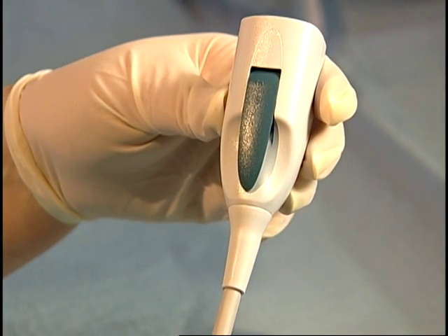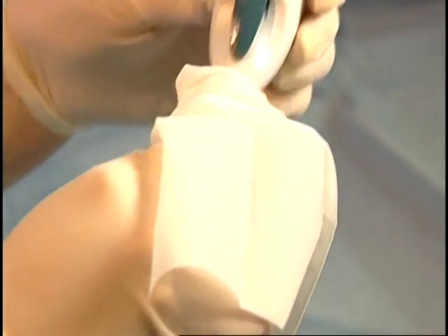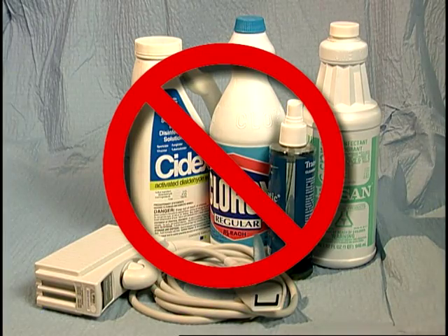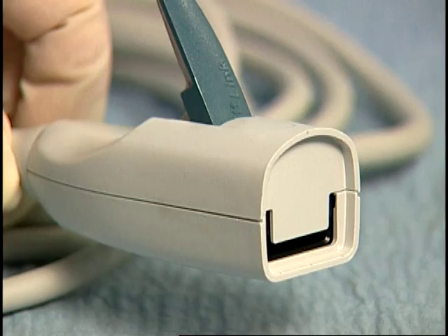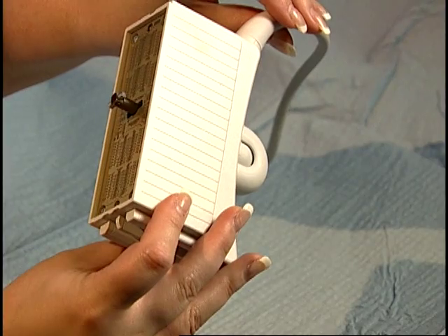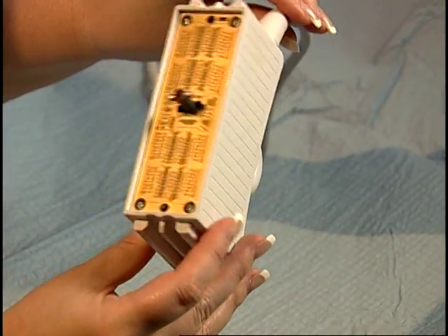The SwiftLink connector is reusable with disinfection only. Do not sterilize it, as most sterilization techniques will cause damage to the internal parts. When disinfecting the SwiftLink connector, ensure that disinfection fluids do not enter the handle lever or locking mechanism, as this may also cause damage to the internal parts.